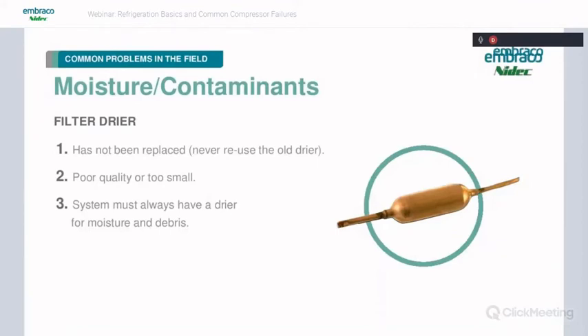And about that dryer, definitely want to change that dryer. I don't think anyone's ever reusing an old dryer, but if anyone's ever thinking about it, definitely don't do that. It can only absorb the moisture once, and it's saturated. We want to make sure we size it correctly, not too small, and also don't put a giant dryer on a tiny system that can hold almost the full charge in the dryer. And that's basically it. The dryer protects the system from any excess moisture that's left over from the evacuation process and debris. So it's very important.